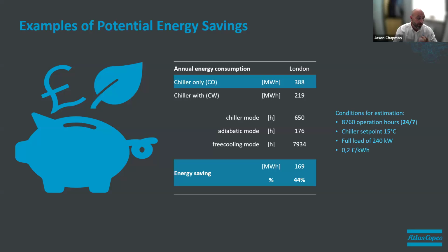A great example on your screens at the moment is using chiller mode for 650 hours a year. Adiabatic modes, once again depending, is only about 176 hours per year. Not so much in this country, because we don't have the extremes of high temperatures. But the best one we can utilize in this country is the free cooling mode: the majority of the year, 7,900 plus hours per year of free cooling. So we're using nature to its advantage.